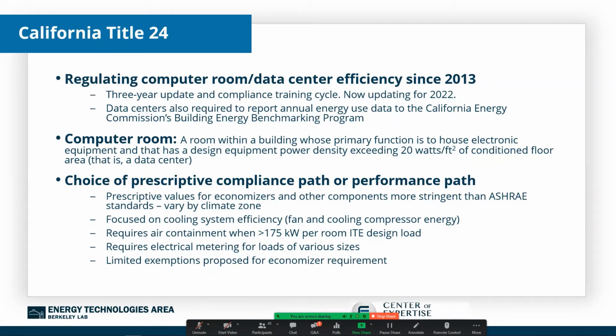California does define computer rooms and data centers somewhat differently than ASHRAE does. In essence, the density thresholds are about the same, but a computer room is inherently part of a data center in the California definition. So California's approach is similar to a combination of ASHRAE 90.1 and 90.4, in that there is a prescriptive path and then there is a performance path.